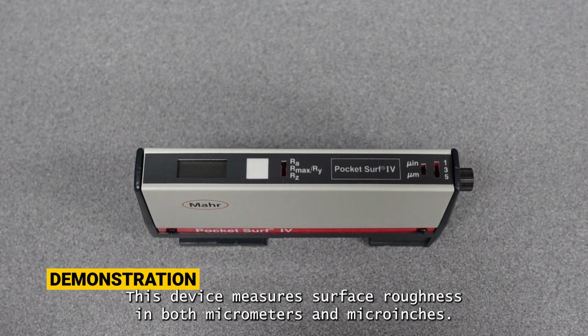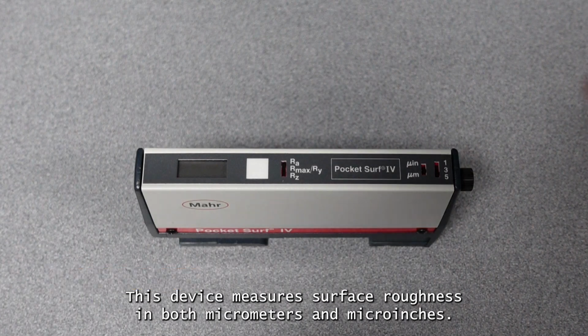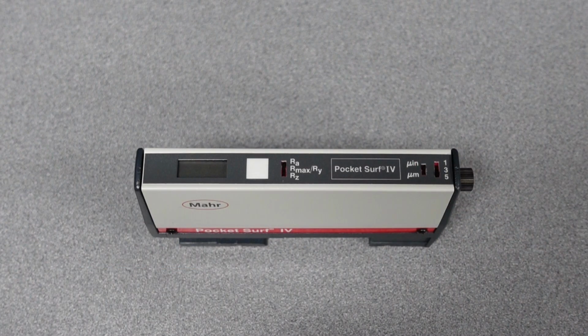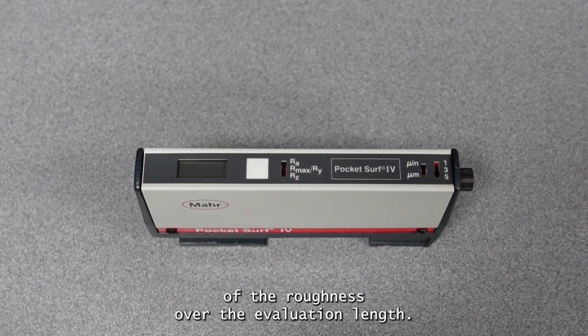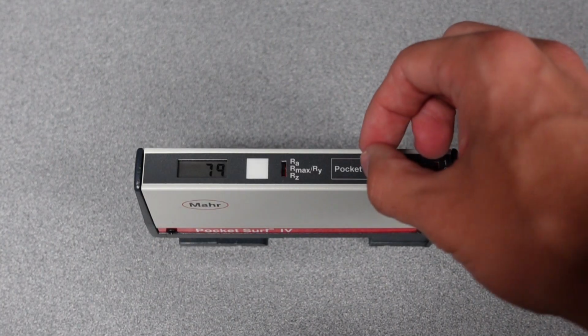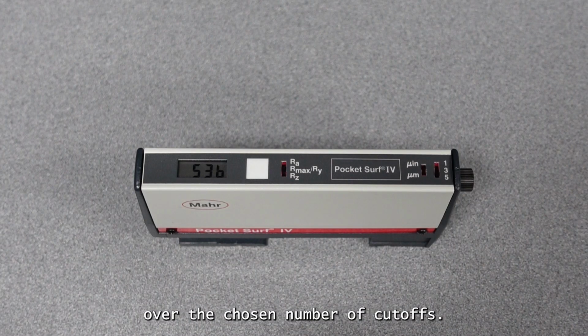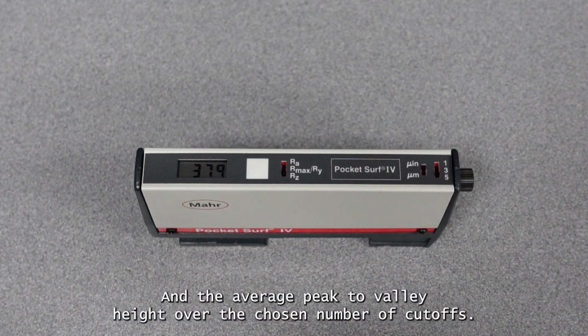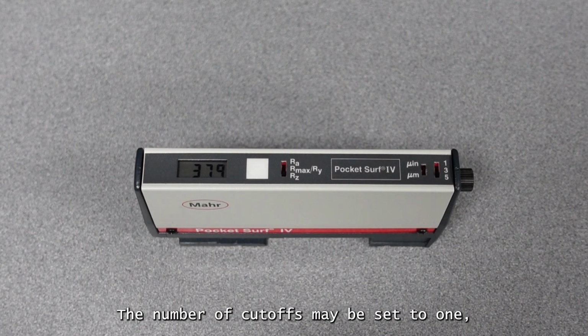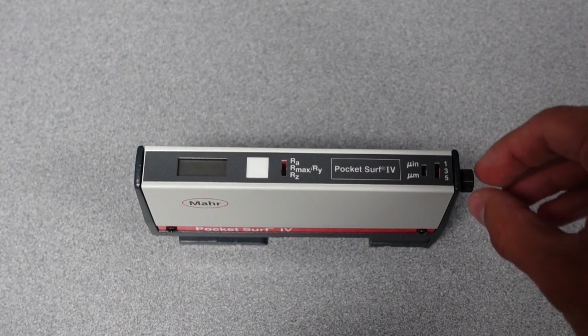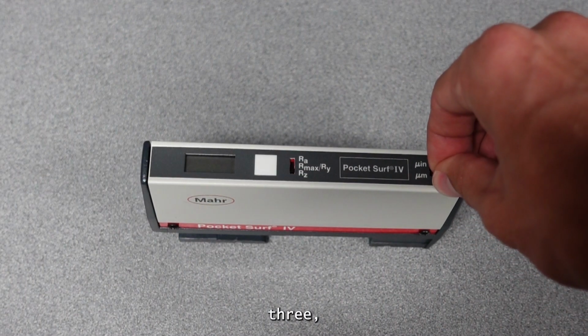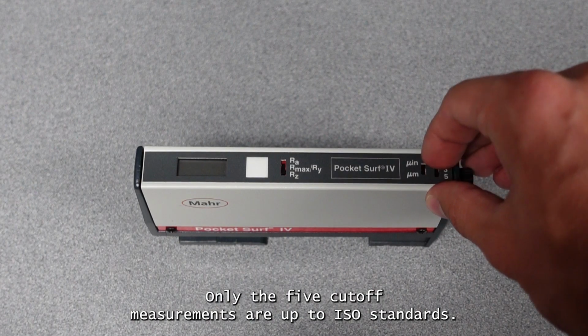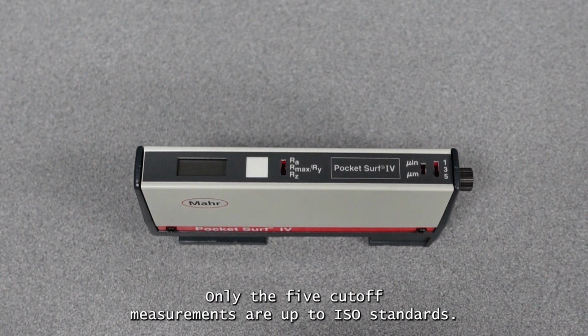This device measures surface roughness in both micrometers and microinches. It will display the arithmetic average of the roughness over the evaluation length, the maximum peak to valley height over the chosen number of cutoffs, and the average peak to valley height over the chosen number of cutoffs. The number of cutoffs may be set to 1, 3, or 5. Only the 5 cutoff measurements are up to ISO standards.